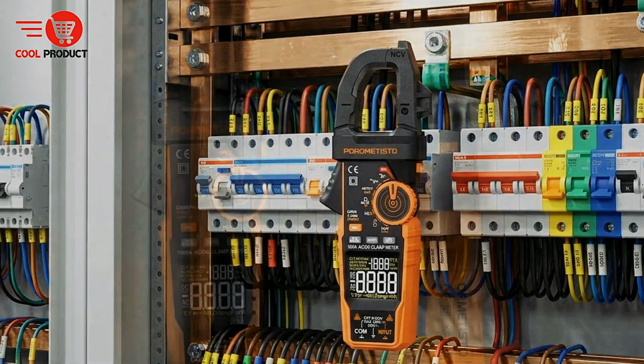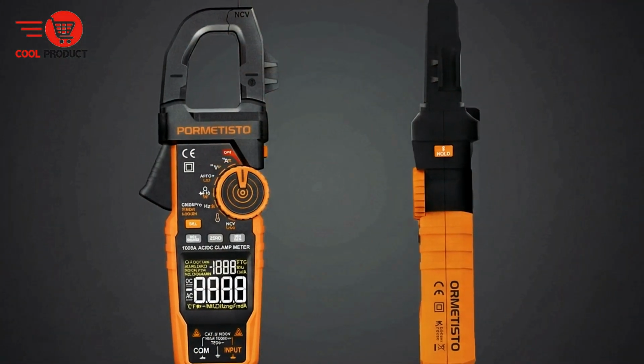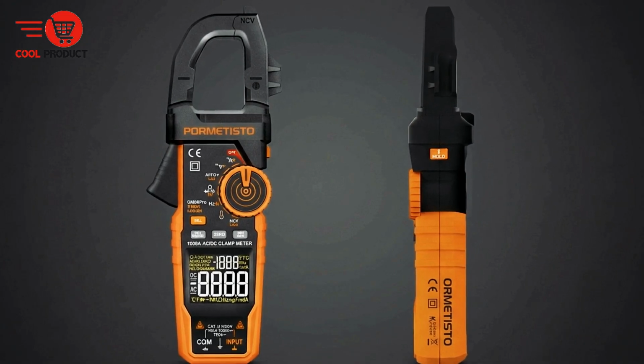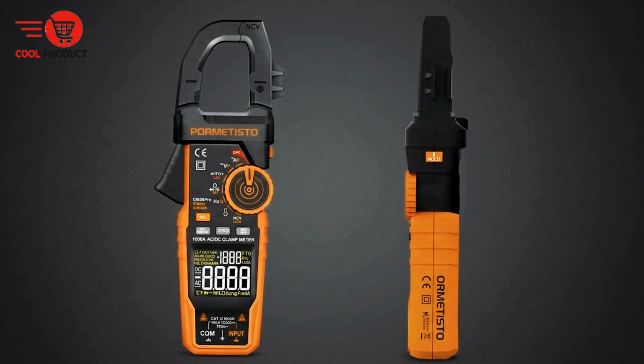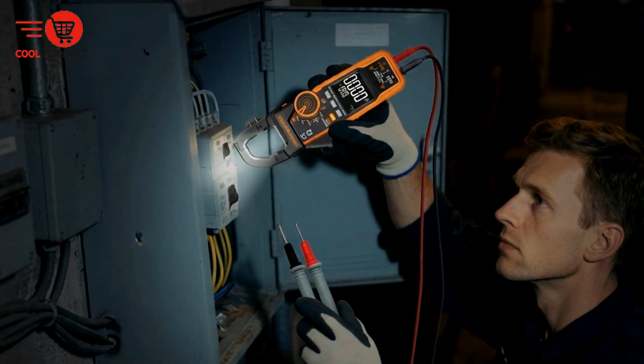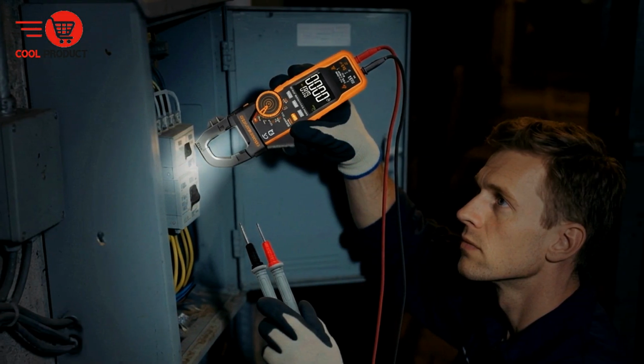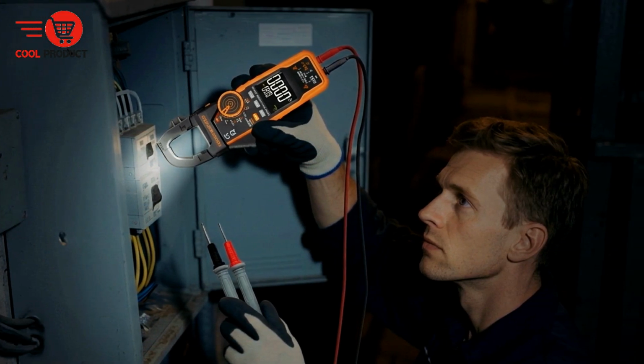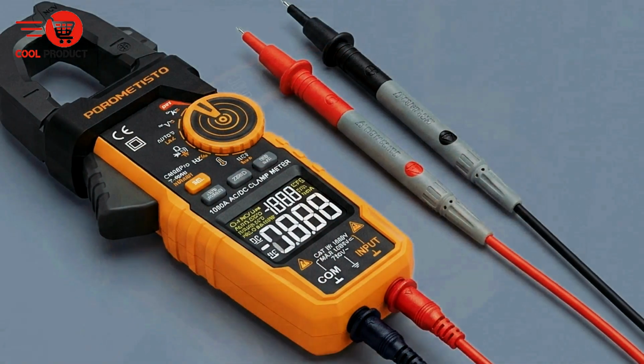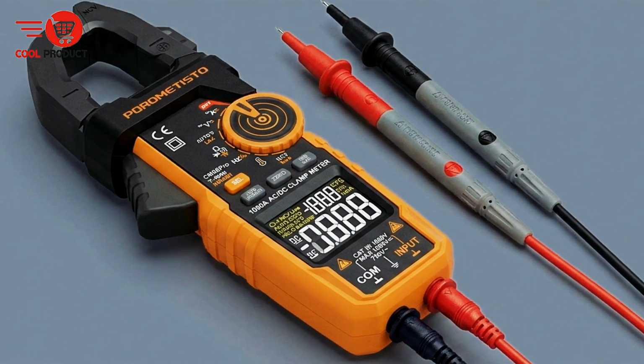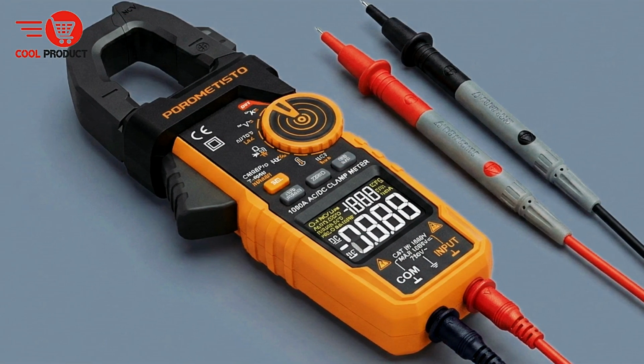It also comes packed with advanced functions like Inrush for measuring startup current, VFD mode for variable frequency drives, LoZ mode to reduce ghost voltage readings, and NCV detection so you can check for live wires without direct contact. These features make troubleshooting faster and much safer.